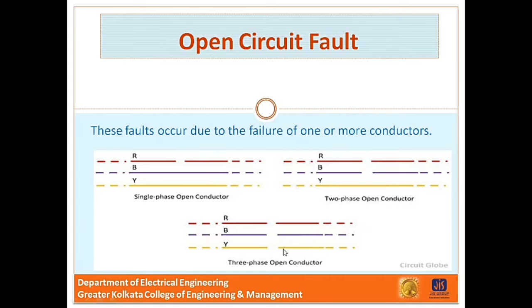Now in the first picture, you see that one line is broken, so we call it a single phase open conductor type fault, and the other two lines are in healthy condition. In the second picture, we see that two lines are broken and the third line is in healthy condition, so we call it a two phase open conductor. And in the last picture, all three lines are open. The first two cases are examples of unbalanced faults, and the last case is an example of a balanced fault.